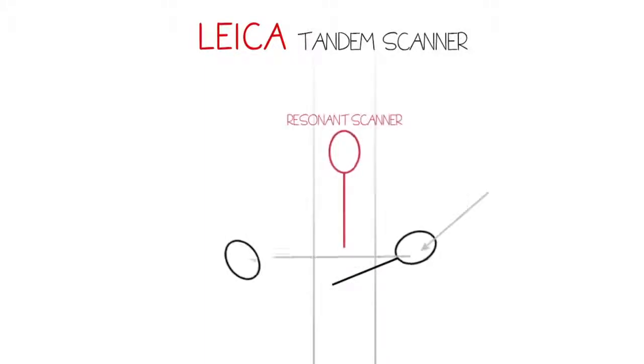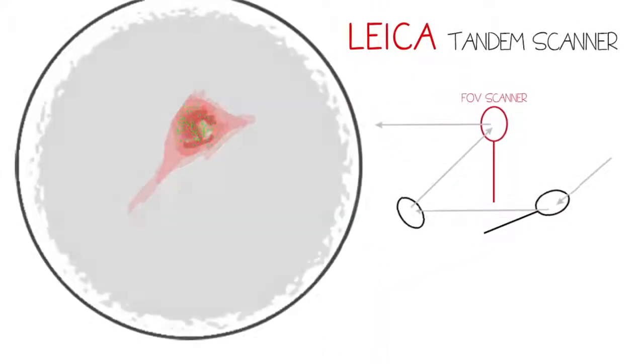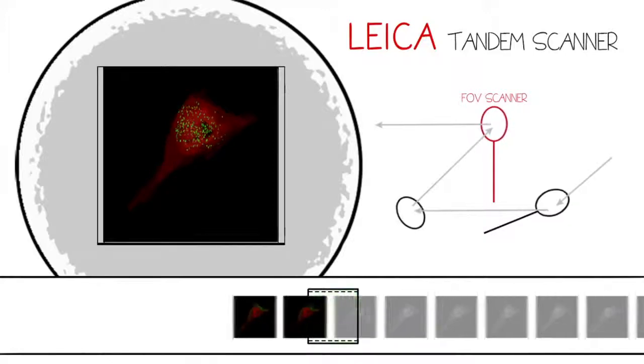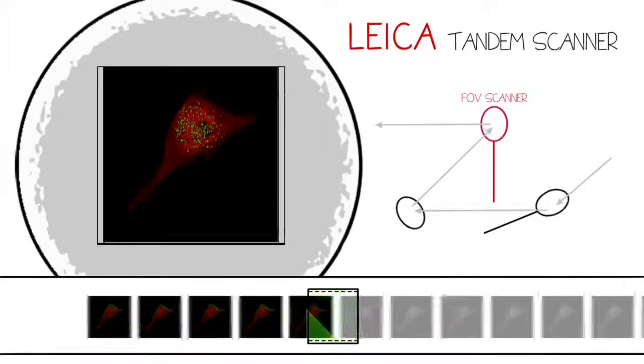Leica's Tandem Scanner eliminates the need for compromise by providing two scanners in one system. This allows you to optimize acquisition parameters based on your experimental needs. The Leica TCS SP8 combines the FOV scanner for the widest field of view and image format with the second high-speed resonance scanner.